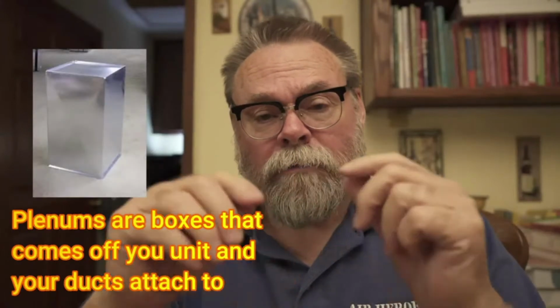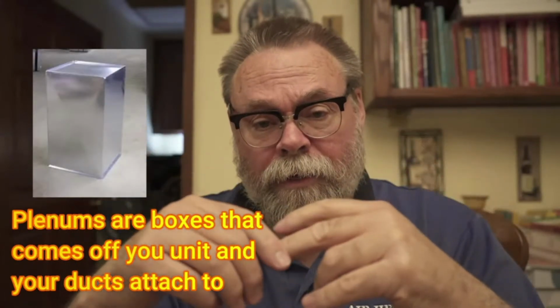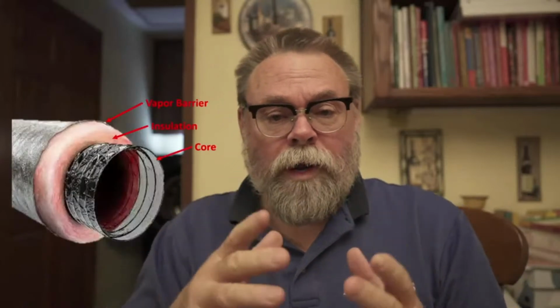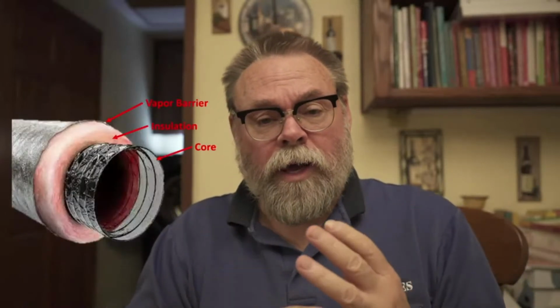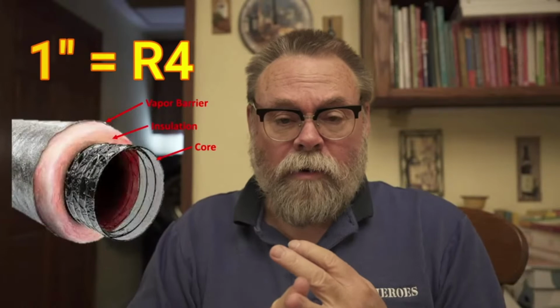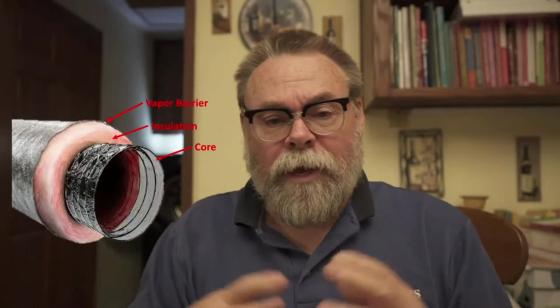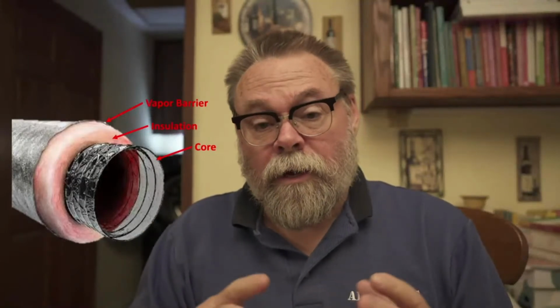Hi, Mitch Bailey here. I want to talk about duct insulation, specifically about some insulation on plenums and your ductwork. Now, all flex duct comes insulated. We buy it with 1 inch, 1.5 inch, or 2 inch. 1 inch insulation is R4.2. We can't use it anymore. That's probably what's been in your house for decades if you have existing flex duct.